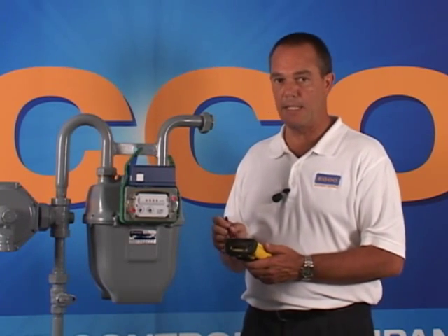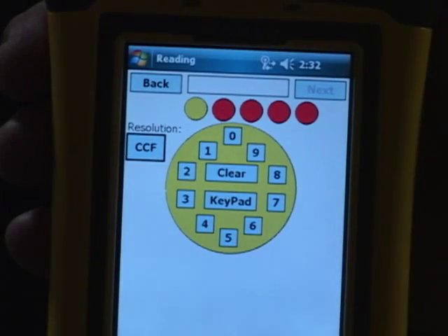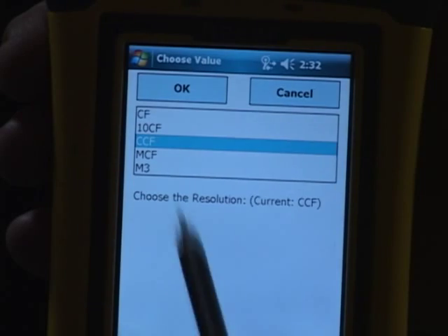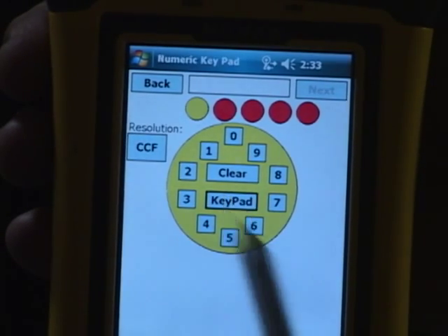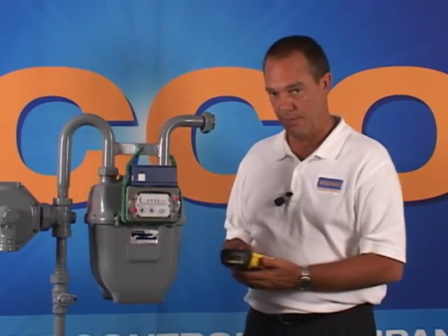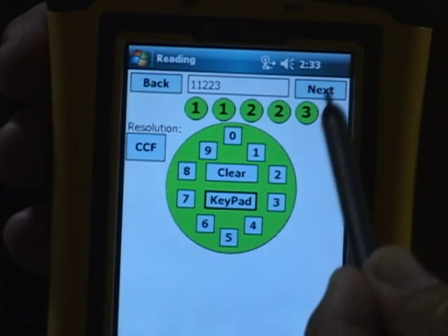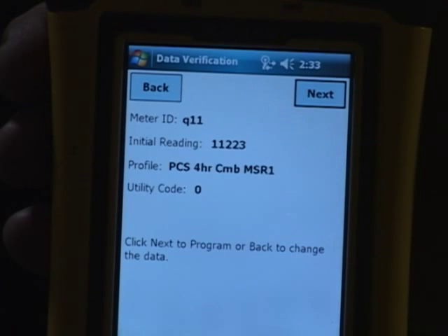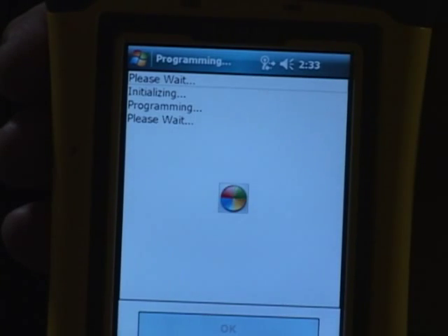Enter the meter ID, which is typically on the badge on the gas meter. Select the resolution — it's going to be CCF. Enter Keypad. Enter the index reading as it is on the meter index itself. Select OK. Now this is your last chance to confirm that your settings are correct prior to programming. Select Next and wait for the programming device to tell you it's been successful.